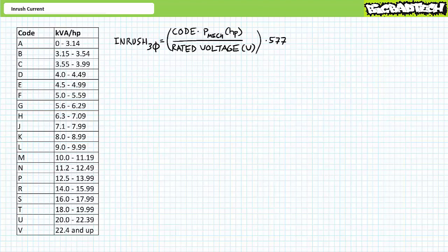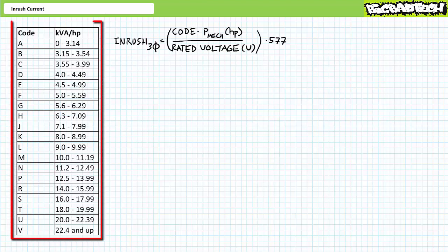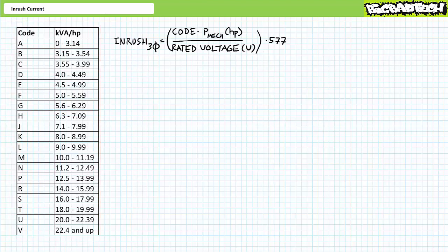Recall in the motor nameplates lecture available at the Big Bad Tech channel, we briefly examined some of the locked rotor code entries on the motor nameplate. The locked rotor code, sometimes called the kilovolt ampere per horsepower constant, is a letter that represents a range of numerical values. These numerical values, along with power and voltage data, are then entered into a formula to calculate the anticipated inrush.